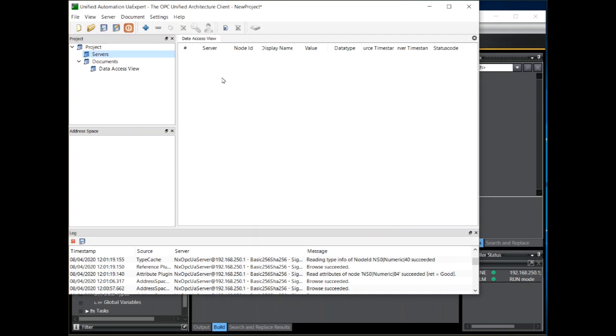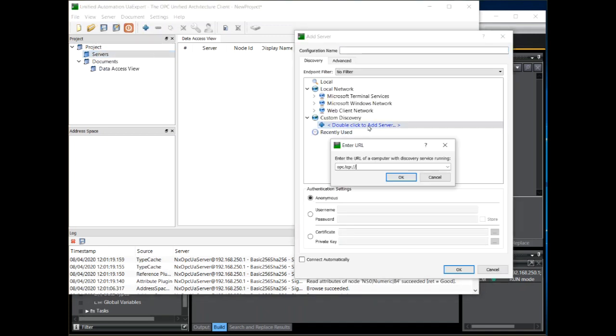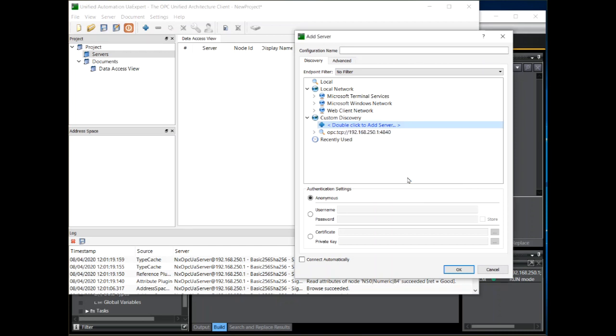We can now add a connection to our NX102 OPC UA server. To do that click on server, add, double click here, and enter the endpoint which is the IP address of the NX102 together with the 4840 port number. Click on OK.